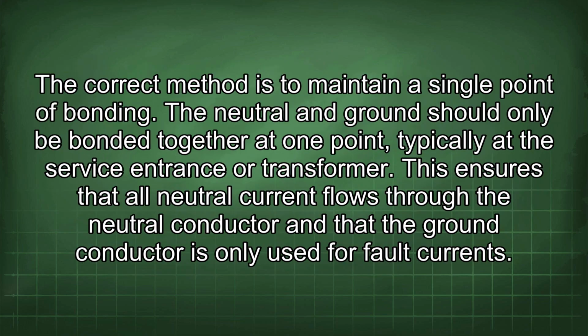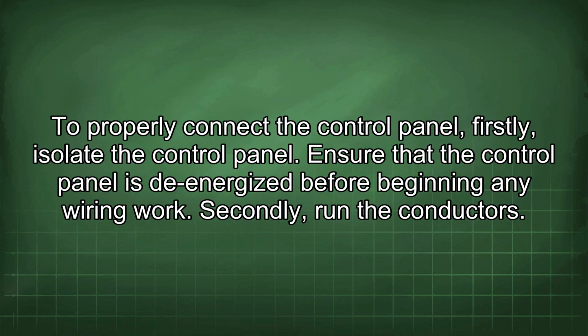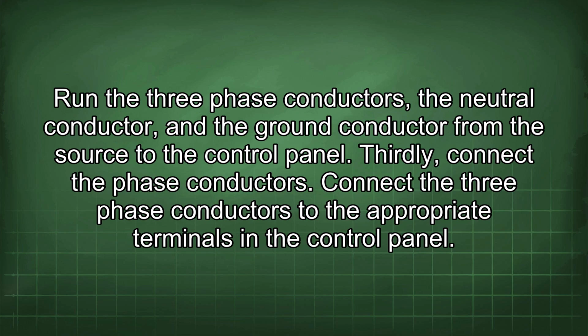The correct method is to maintain a single point of bonding. The neutral and ground should only be bonded together at one point, typically at the service entrance or transformer. This ensures that all neutral current flows through the neutral conductor and that the ground conductor is only used for fault currents. To properly connect the control panel, firstly, isolate the control panel. Ensure that the control panel is de-energized before beginning any wiring work. Secondly, run the conductors. Run the 3-phase conductors, the neutral conductor, and the ground conductor from the source to the control panel.